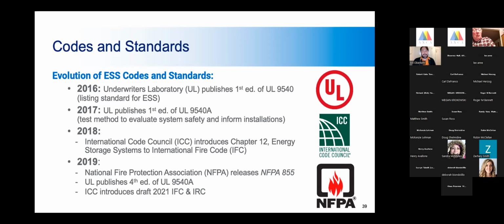What we see written into the fire code over and over again is large-scale fire testing, which is synonymous with UL 9540A - they mean the same thing. The exception is often 'unless large-scale fire testing says otherwise.' So the code official or fire marshal evaluating for fire code compliance looks at this 9540A report, which documents how the system behaves in the event of a catastrophe, and makes siting decisions based on that.